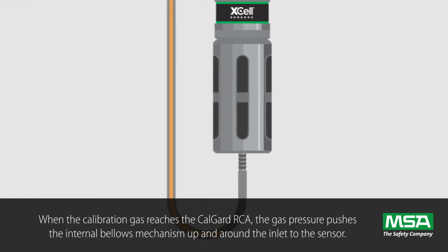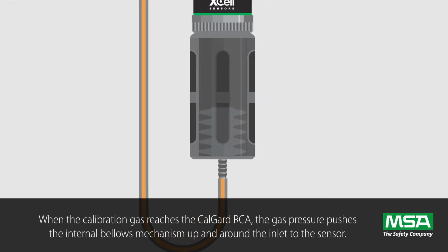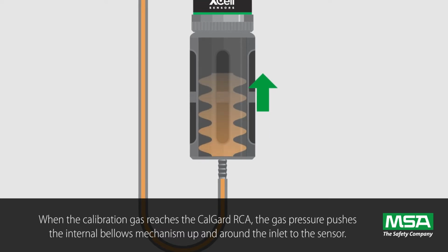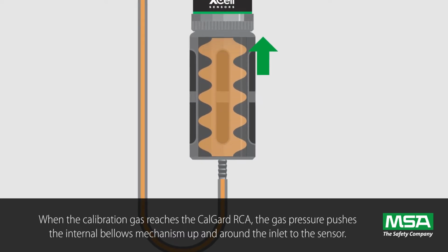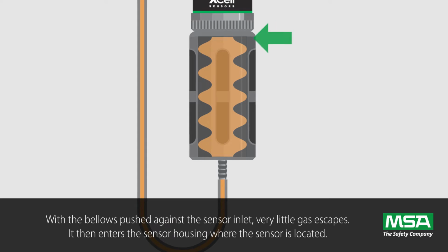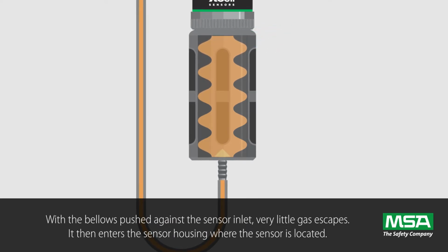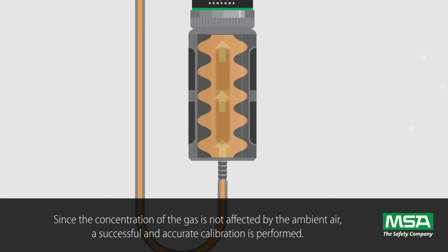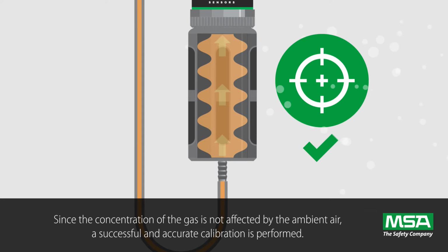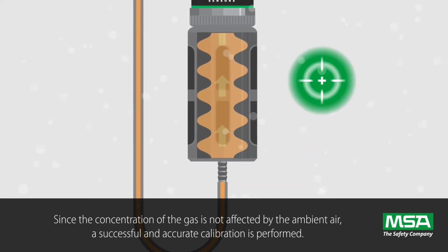When the calibration gas reaches the CalGard RCA, the gas pressure pushes the internal bellows mechanism up and around the inlet to the sensor. With the bellows pushed against the sensor inlet, very little gas escapes. It then enters the sensor housing where the sensor is located. Since the concentration of the gas is not affected by the ambient air, a successful and accurate calibration is performed.